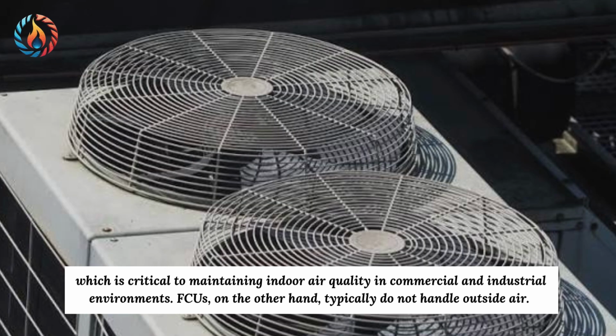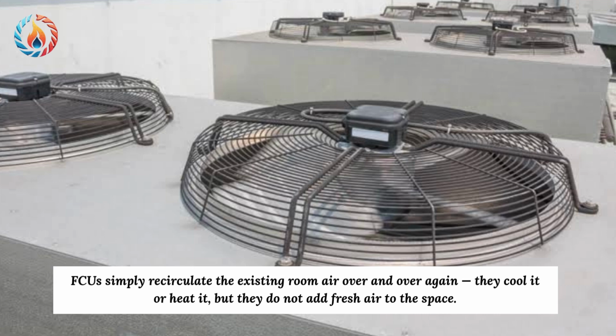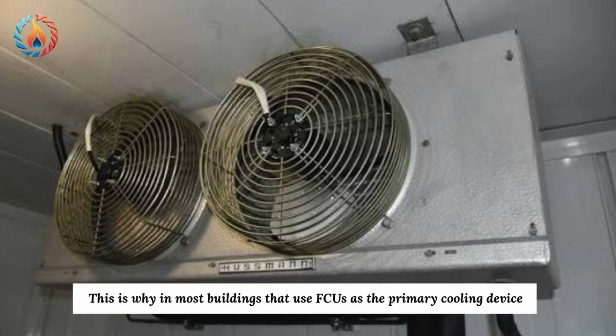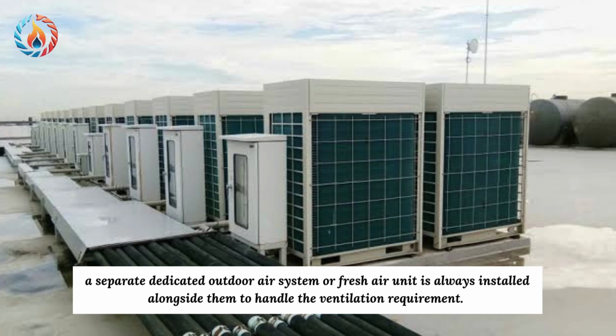FCUs, on the other hand, typically do not handle outside air. FCUs simply recirculate the existing room air over and over again. They cool it or heat it, but they do not add fresh air to the space. This is why in most buildings that use FCUs as the primary cooling device, a separate dedicated outdoor air system or fresh air unit is always installed alongside them to handle the ventilation requirement.